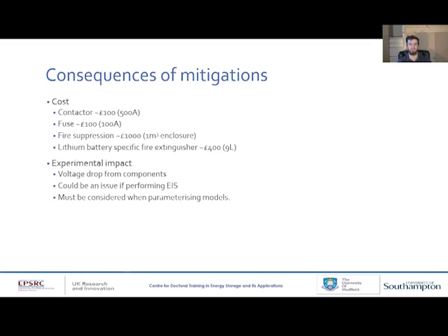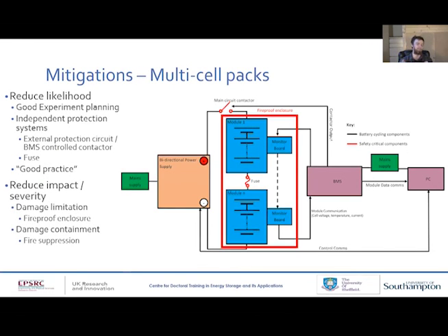Yeah, so specifically thinking about the BMS systems I've been using, they independently control the contactor, i.e. they're measuring the voltage, and if something's wrong, the BMS itself will turn off the contactor, and that has nothing to do with this communication. Obviously it's all to do with this communication bit, but then the PC should be able to quite easily detect any discrepancy between what the power supply is reading and the BMS, and that's how I've justified it as being independent. Does that answer your question? Yeah, I think so. Yes.